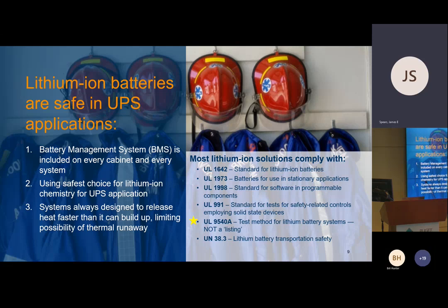Again, the system is designed by the manufacturer to release heat faster, even under adverse conditions, than it can possibly build up. That limits the possibility of thermal runaway.